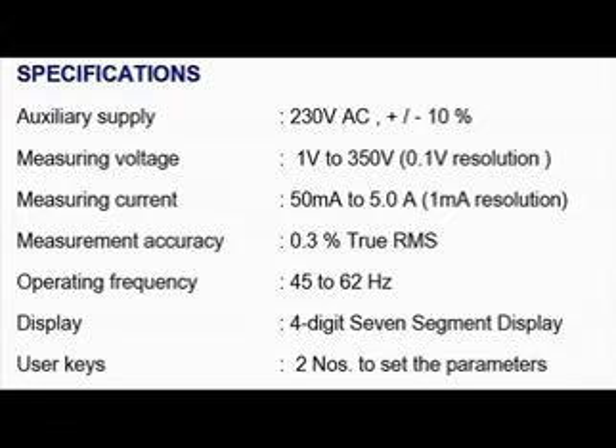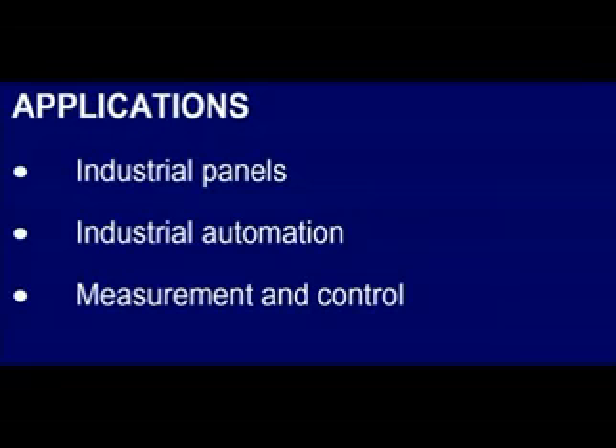The operating frequency for the true RMS will go from 45 to 62 Hertz. Again, in lab tests, we have seen it will give the correct true RMS value up to 100 Hertz. The display is a simple 4-digit 7-segment display, and we have 2 keys for calibration and setting parameters. The main applications for the digital panel meter will come in the industrial domain, in industrial panels for industrial automation, and in industrial measurement and control.